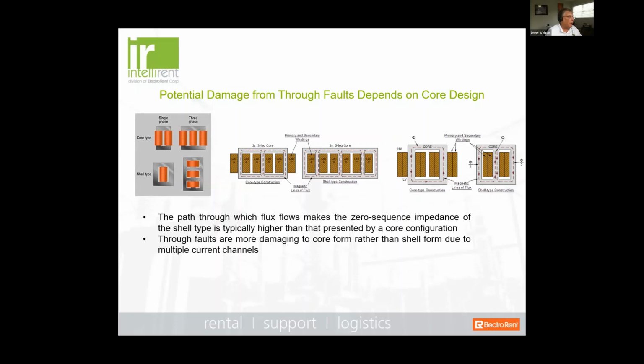And one of the things that's important to understand is that the potential damage from a through fault depends somewhat on core design, and the path through which the flux flows makes the zero sequence impedance of the shell type transformer higher than that of a core form configuration. So through faults are typically more damaging to core form rather than the shell form, due to the multi-current channels that we see in a core type construction. Now, word of caution, that doesn't mean this type of core design can't be subjected to damage from a through fault.